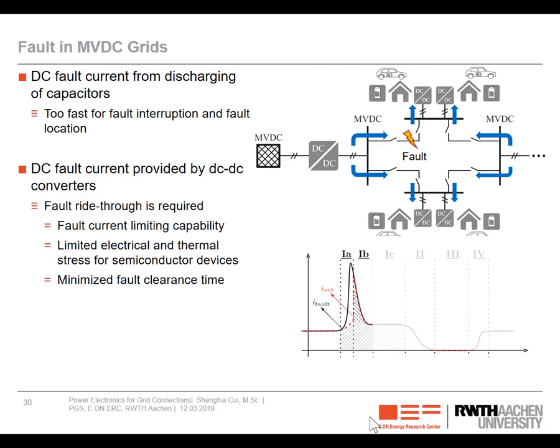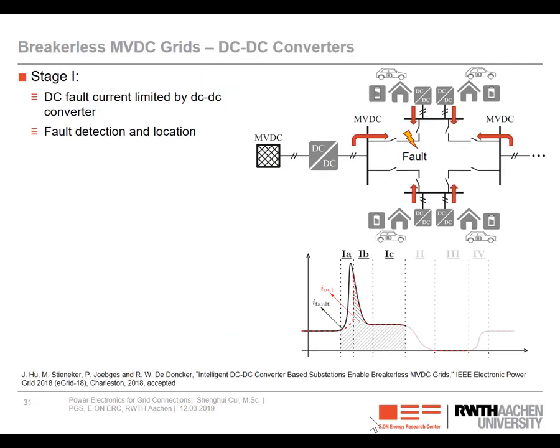And in the meantime, we need to guarantee that these DC converters are operating within the electrical and thermal limits. Otherwise, the converters will be destroyed. And we hope to minimize fault clearance time. Due to the immature and costly MVDC circuit breakers, we developed the breakerless operation scheme, as I will introduce here.